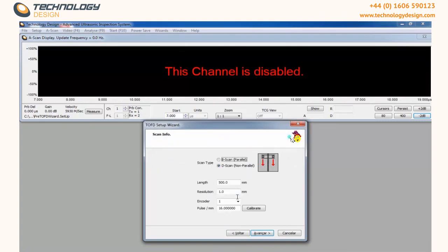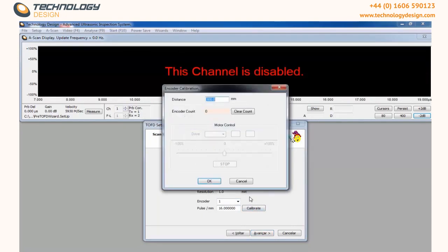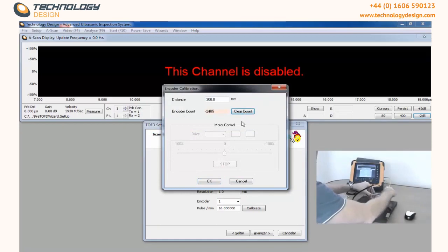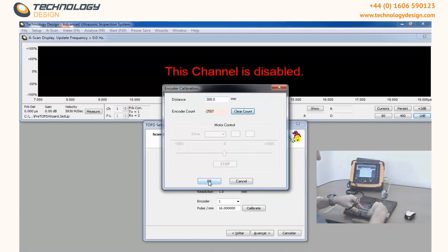In this screen we will calibrate the encoder. Click on Calibrate, position your scanner at zero and click Clear Count. Move your scanner the distance informed above and click OK.